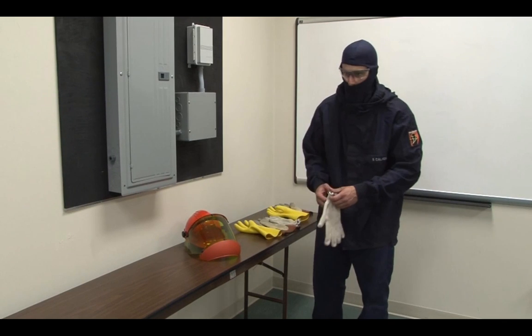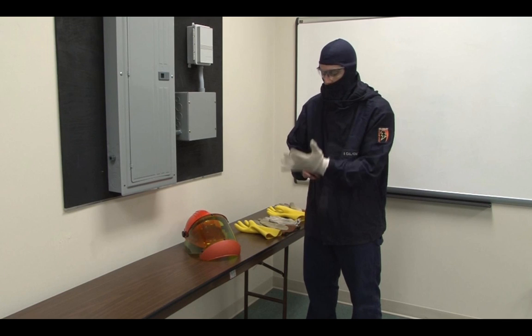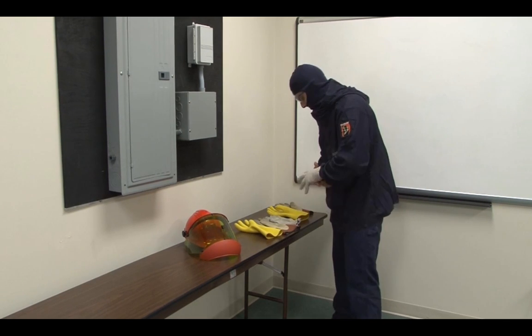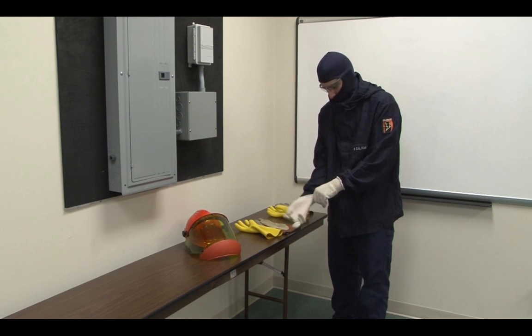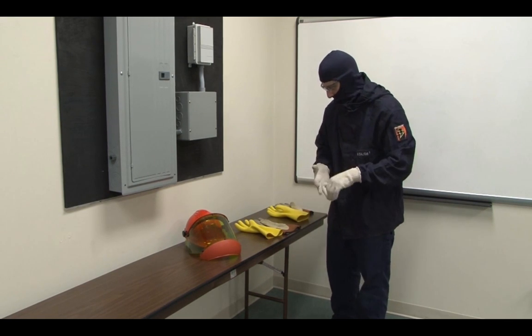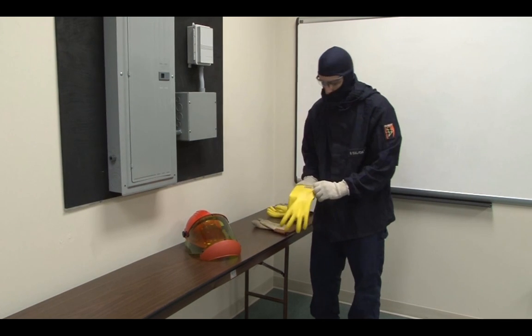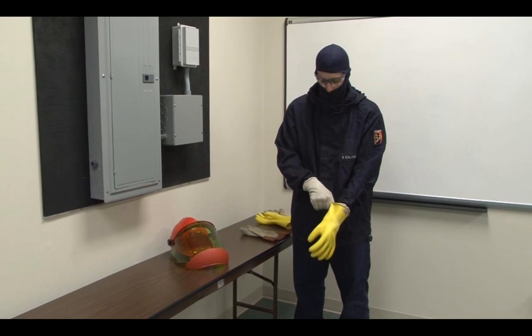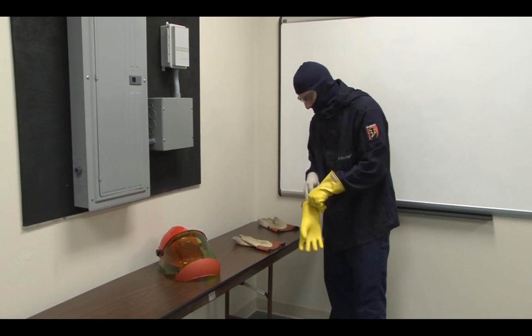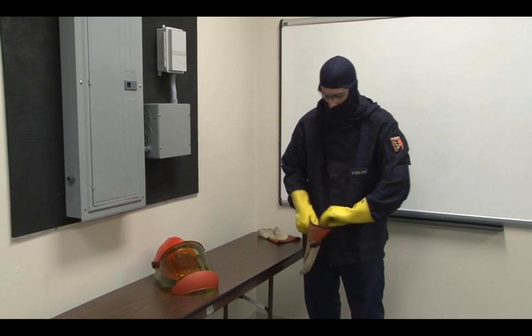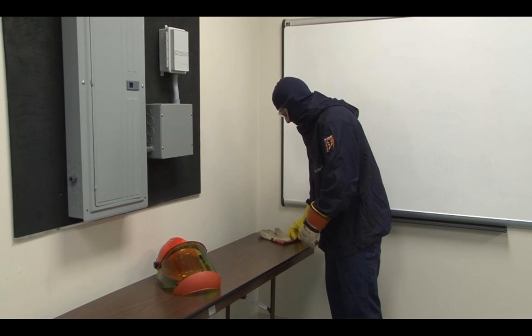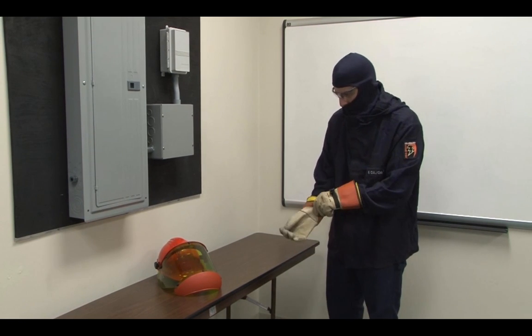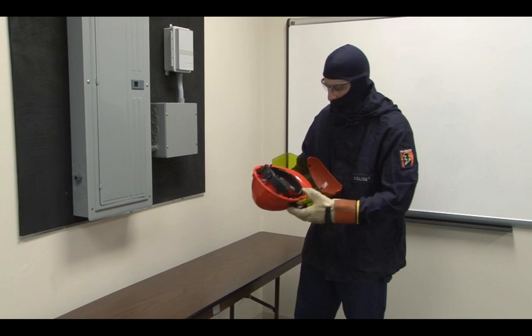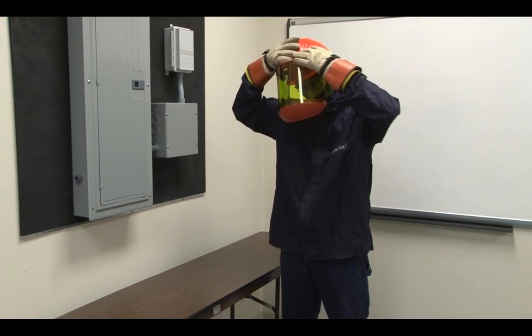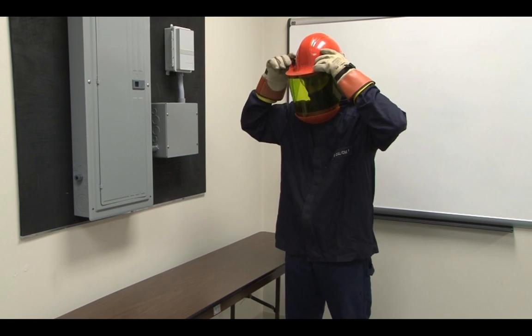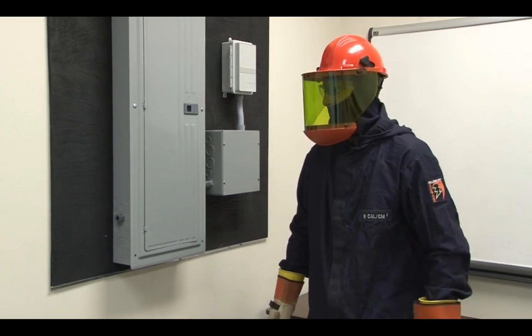And I'll put my first layer of gloves on. These are to absorb the moisture. These are followed by my class 00 500 volt voltage insulators and my leather protectors. And I'm now ready to remove the cover of the energized panel board.